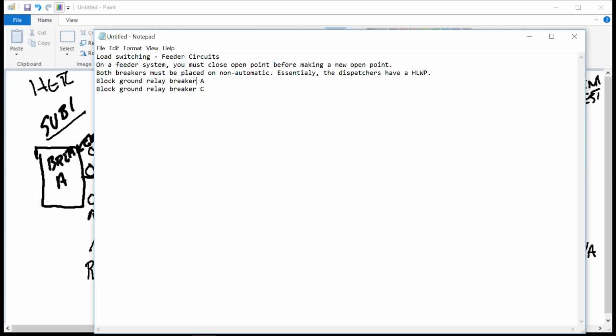Now, this is kind of technical, so think about it a little bit. What do I mean by blocking the relay to start with? Making sure it won't reclose, or That's not a reclosing relay. That's the ground relay. You're on the right track. It's just simply turning it off. Okay? Don't use. Go down to the next one. Turn it off. Don't use. But there's a reason why we don't want the ground relay to recognize anything. Anybody got any ideas on that?